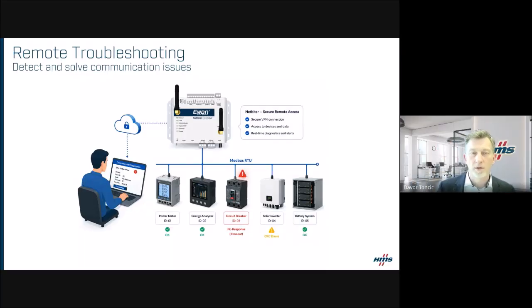Moving in a bit, one part about Modbus, including SunSpec Modbus, is that you can do troubleshooting of a Modbus connection line remotely. Let's say you're running Modbus RTU with different devices connected. You can troubleshoot based on whether you get timeouts, CRC errors, and things like that.